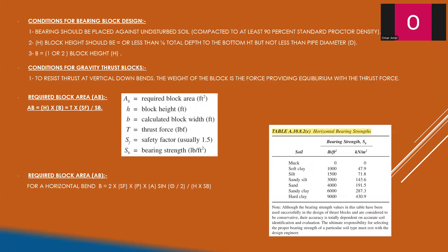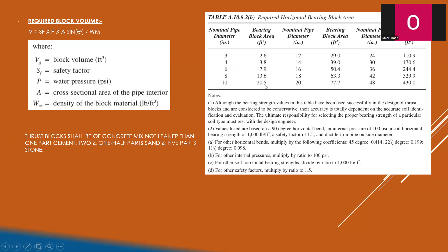The block area can also be extracted from a tabulated table, knowing the nominal pipe diameter. However, note that the tabulated values are based on a 90-degree bend, a 1.5 safety factor, and 100 psi design pressure. If you have different values — such as a 45-degree bend or 120 psi — you must apply correction coefficients listed in the table, depending on the bend angle, internal pressure, and soil bearing strength, to get the exact value of the bearing block area.